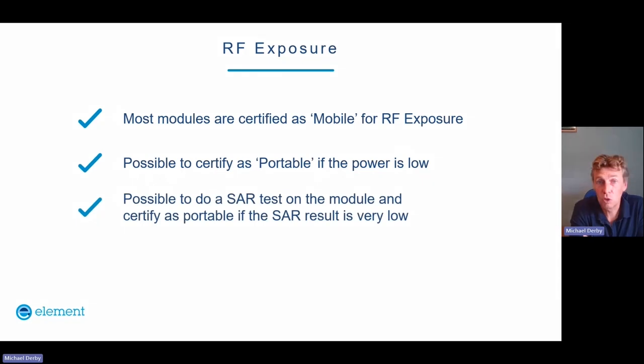It is actually possible to do a SAR test on a radio module. And if the SAR value is low enough, such as below 0.4 watts per kilogram, then it could be certified as a portable device. You still need to do some SAR testing when you install it, but it could still maintain its portable certification. So if the power is really low, or you've done a SAR test on the module, you could assess it as portable.